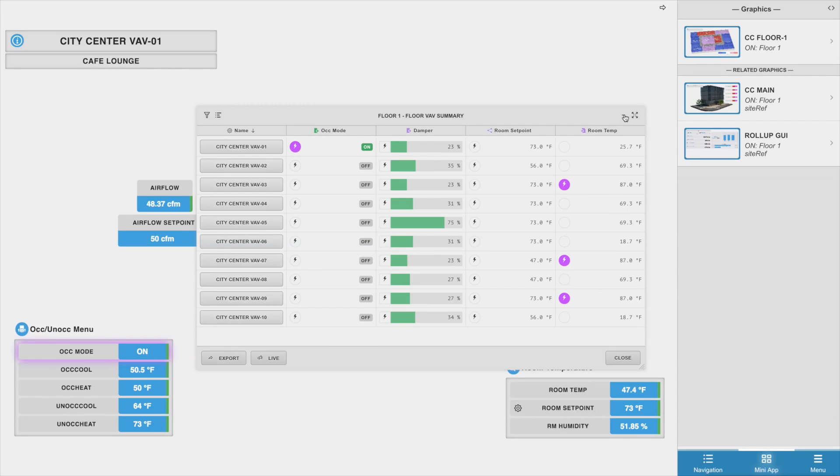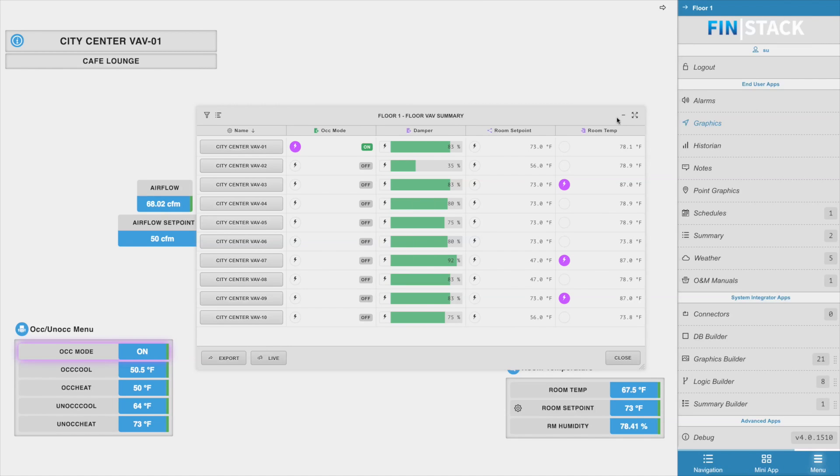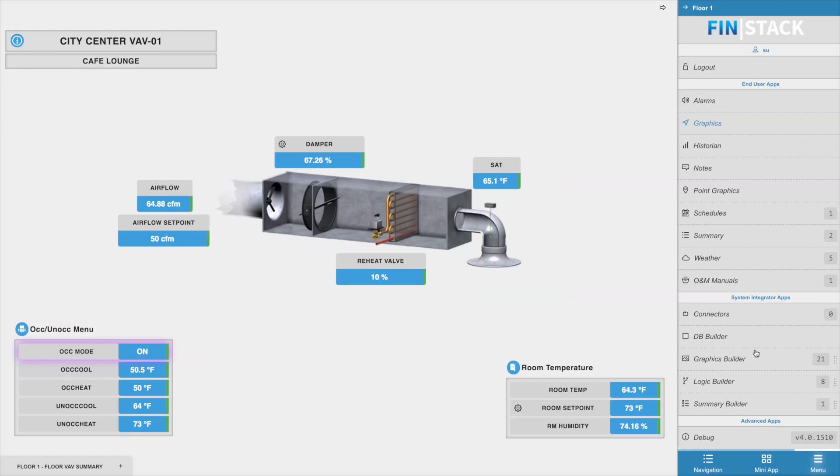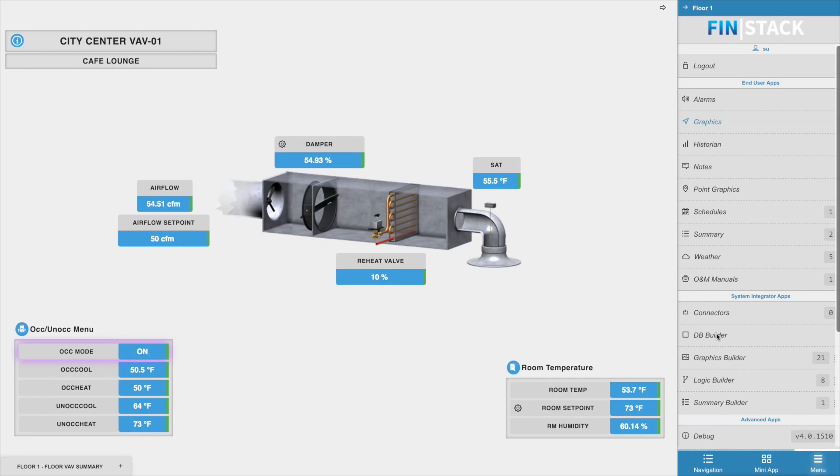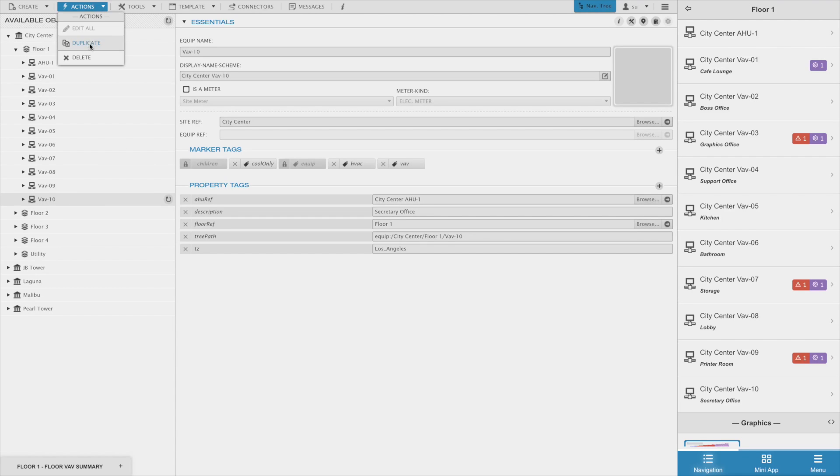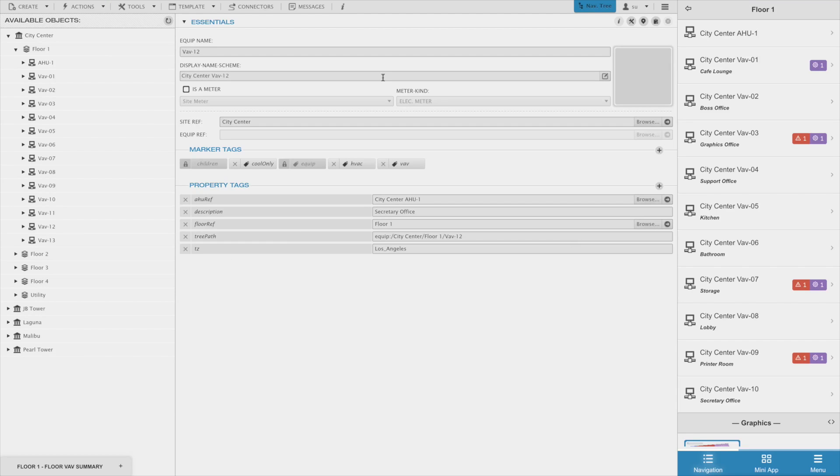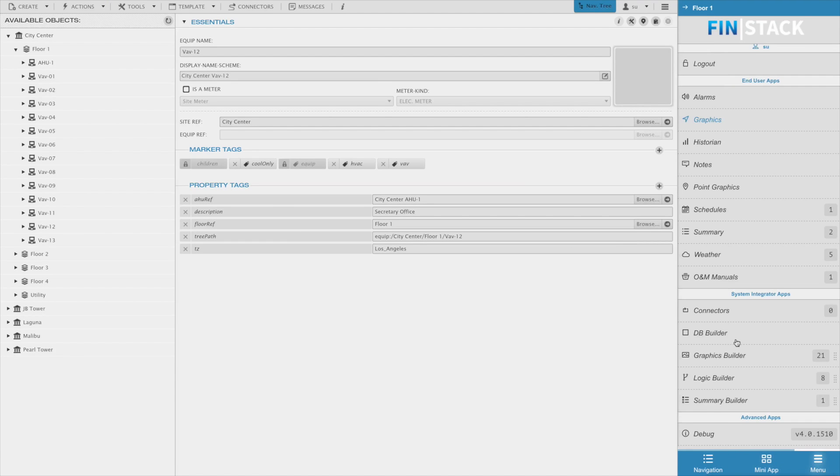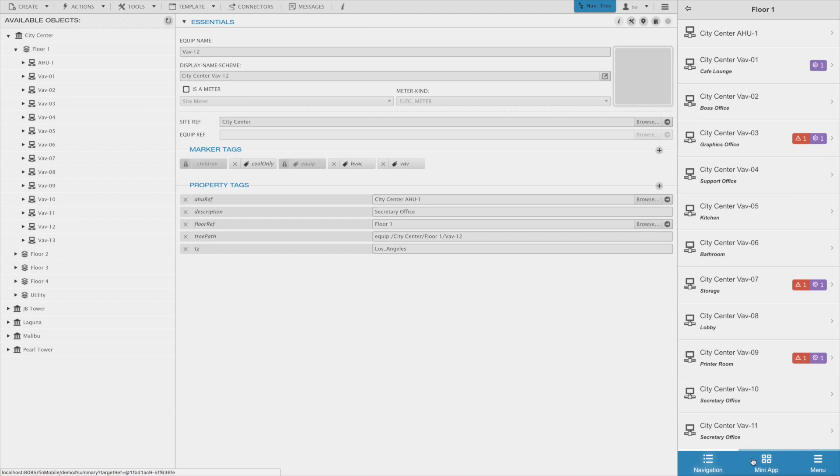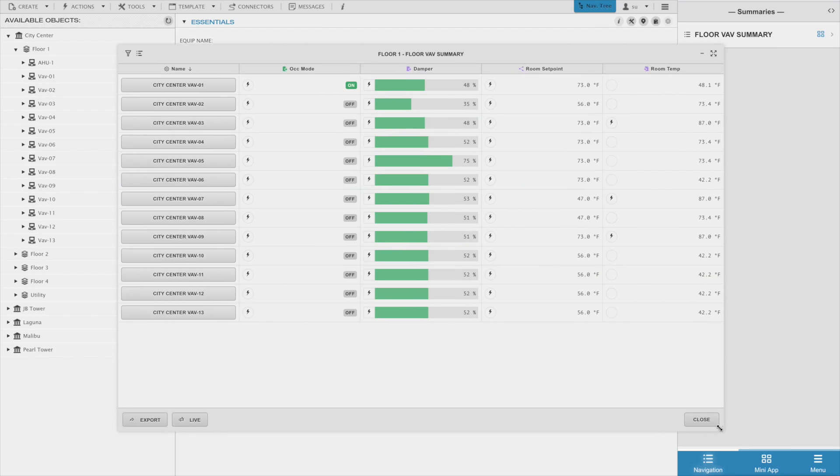Okay, so one last thing about these summaries that are really helpful is that since they are running on tags, anytime a VAV is added the summary will automatically pick it up and include it in the summary. So for example, let's say we're going to add three VAVs to our database. I'll go ahead and go to the db builder and use my duplicate feature just to duplicate my VAV three times. Now when I go back to my summary, you can see that all three of those VAVs were automatically added in the summary without me having to do any additional work.